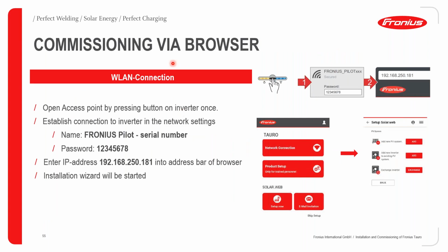You can also do this via a browser using wireless LAN connection, or as you preferably call Wi-Fi. Open, but this time around you have to use a browser. So first off, you need to open your Wi-Fi access point by pressing the button on the inverter once. And immediately you do that, you go to your Wi-Fi settings. You will definitely see the device ID stating Fronius Pilot with the serial number. And then once you select it, you will have to enter a password. And the password, as has always been the case, is 1 straight up to 8. That is 1, 2, 3, 4, 5, 6, 7, and 8.